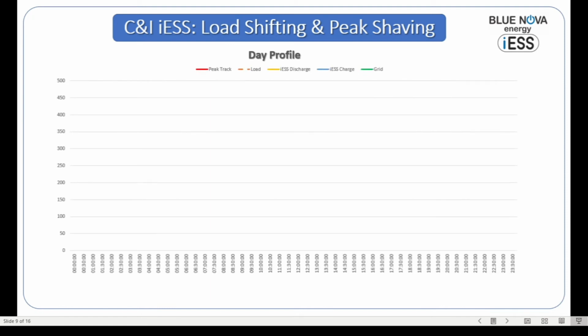So let's see how the load shifting and peak shaving actually works, when it is applicable, and how this leads to the required savings. On this axis we have kVA, or the power requirement of the load, looking at it over a 24-hour period. As an initial condition, we decided to cap the peak demand at 360 kVA during that day. Prior to the iESS system being in action, one can see that we have two places in the day where we exceed the threshold of 360 kVA. And obviously we would like to shave those peaks off and make the savings associated with those two peaks.